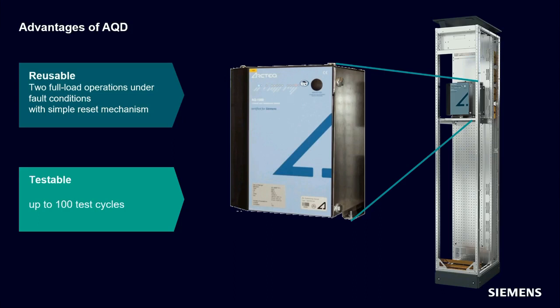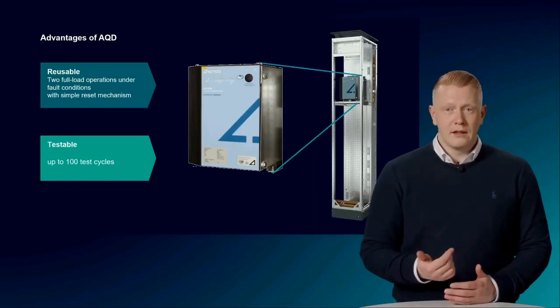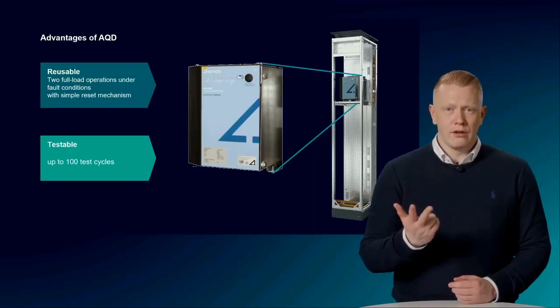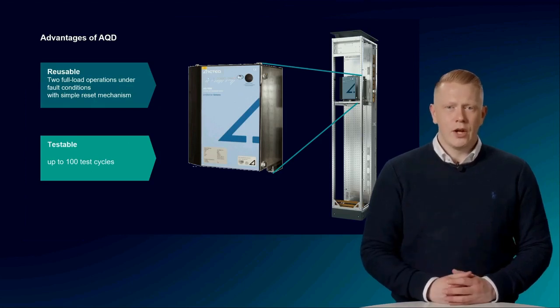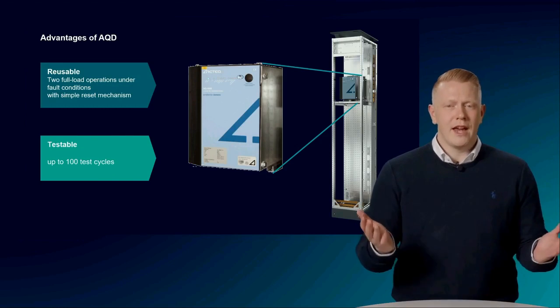As the system can be used up to 690V and 100kA, it can be installed in the majority of applications, ensuring comprehensive protection of the system, related processes, and personnel. The three essential components of an arc fault — light, current rise, and pressure — are detected and evaluated. A shutdown takes place quickly and safely.